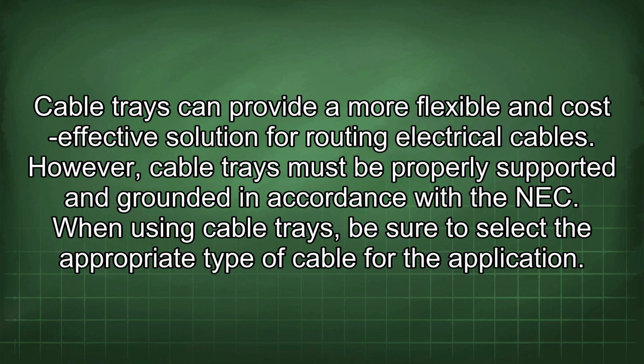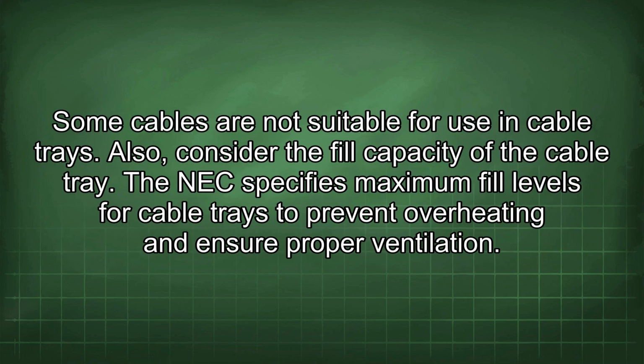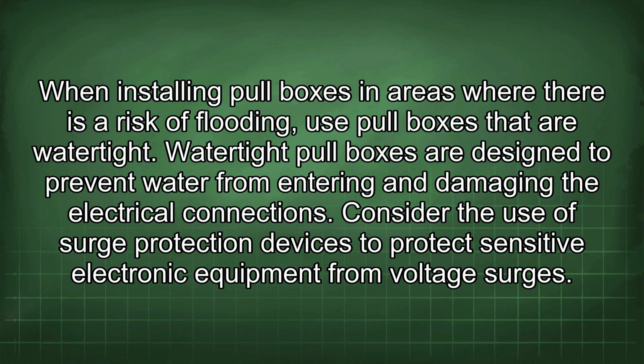However, cable trays must be properly supported and grounded in accordance with the NEC. When using cable trays, be sure to select the appropriate type of cable for the application. Some cables are not suitable for use in cable trays. Also, consider the fill capacity of the cable tray. The NEC specifies maximum fill levels for cable trays to prevent overheating and ensure proper ventilation. When installing pull boxes in areas where there is a risk of flooding, use pull boxes that are watertight. Watertight pull boxes are designed to prevent water from entering and damaging the electrical connections.